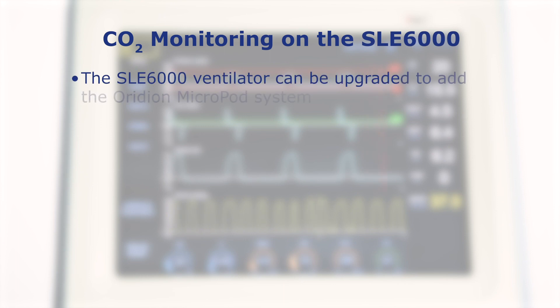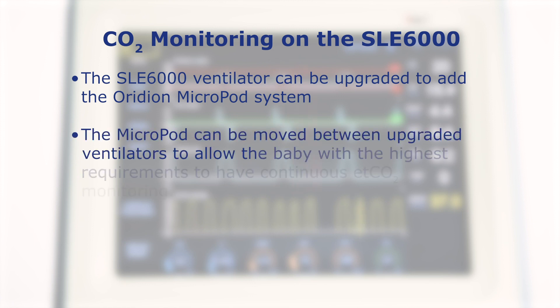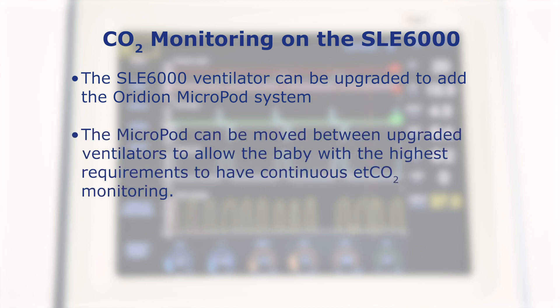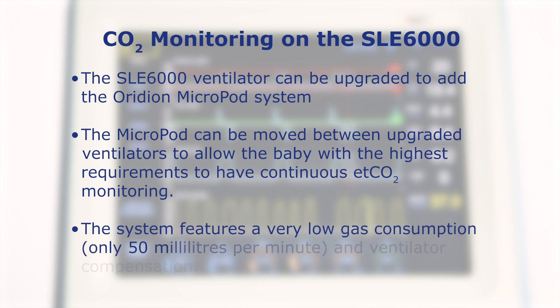The SLE6000 ventilator can be upgraded to add the Oridion MicroPod system. The Micropod can be moved between upgraded ventilators to allow the baby with the highest requirements to have continuous ETCO2 monitoring. The system features very low gas consumption of only 50 millilitres per minute, with ventilator compensation.